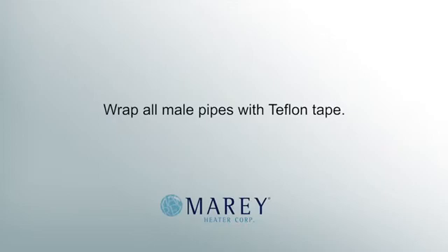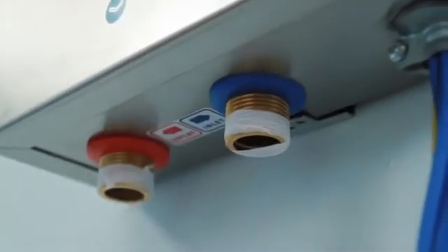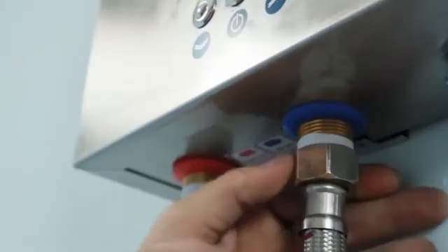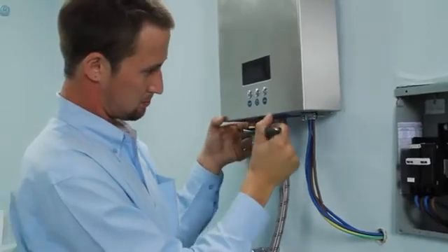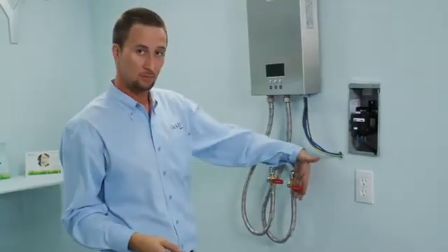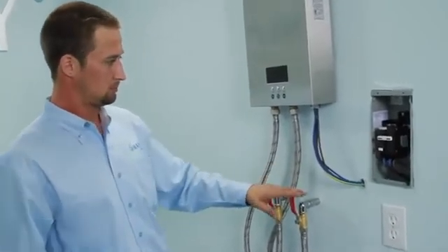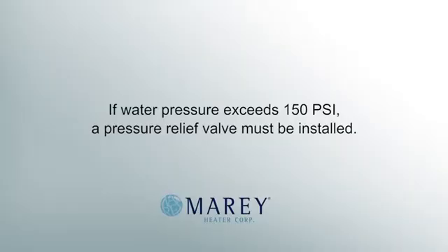Wrap all male pipes with Teflon tape. After the water connections are made, you should turn on the hot water tap to purge all air from the pipes. Once the water is flowing consistently, check for leaks and correct as necessary. If the water pressure exceeds 150 psi, a pressure relief valve must be installed.